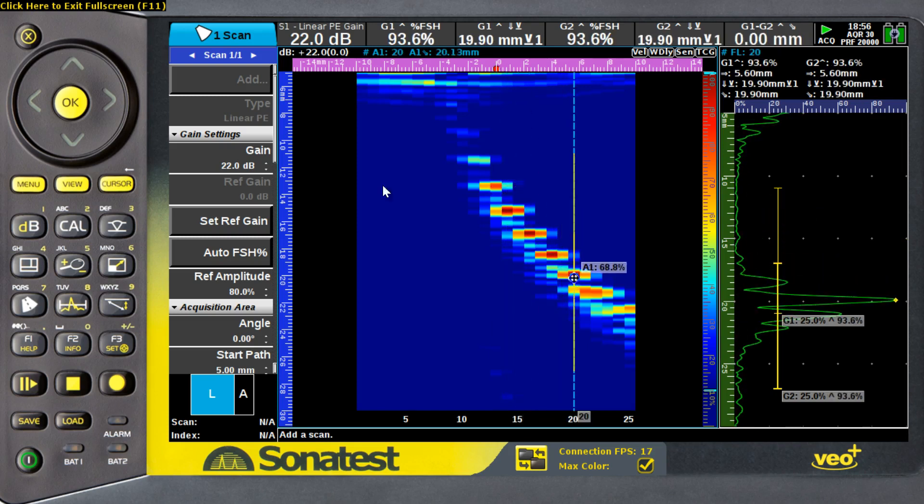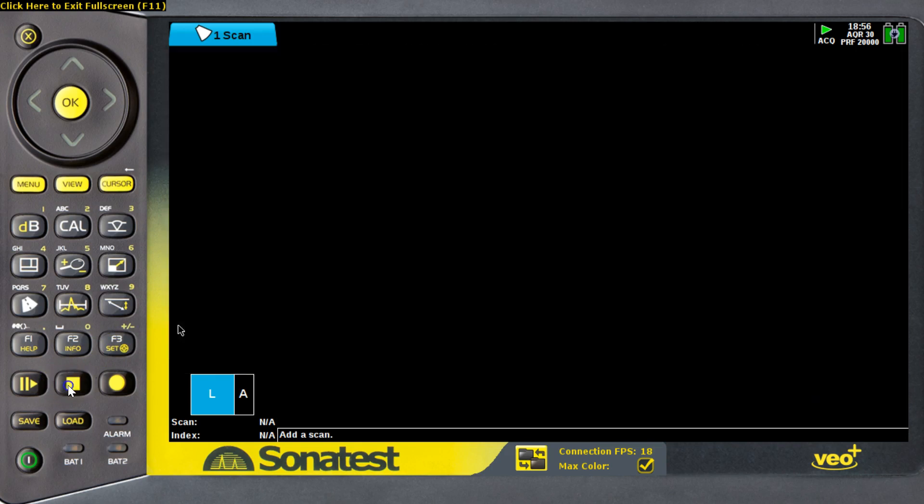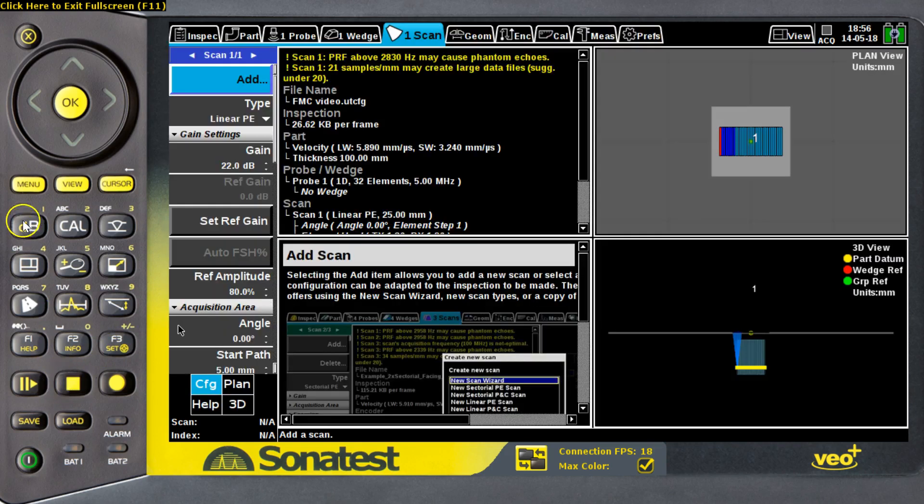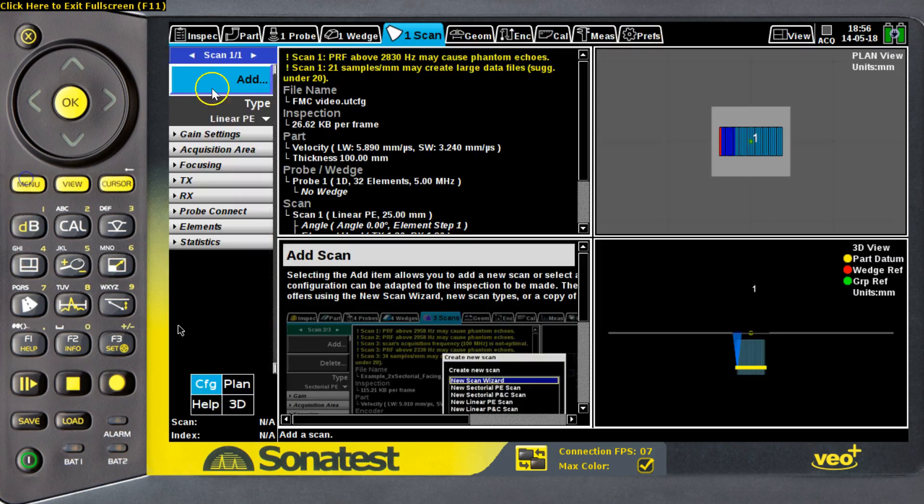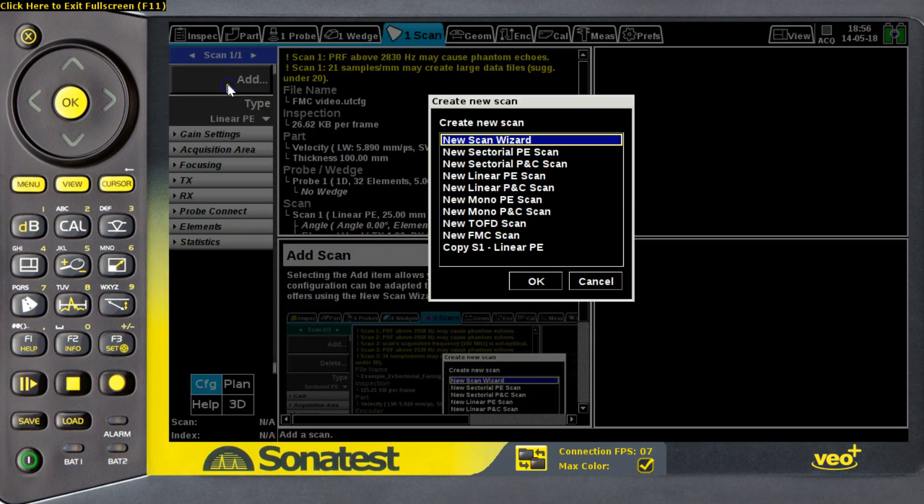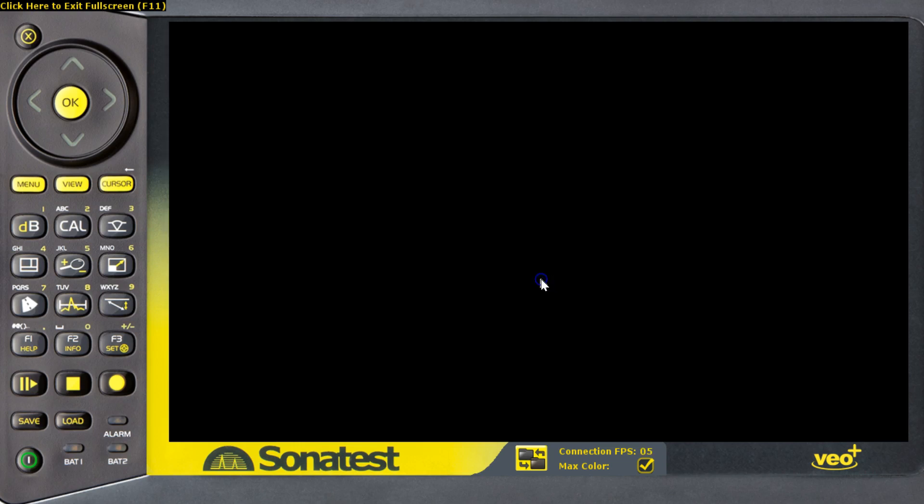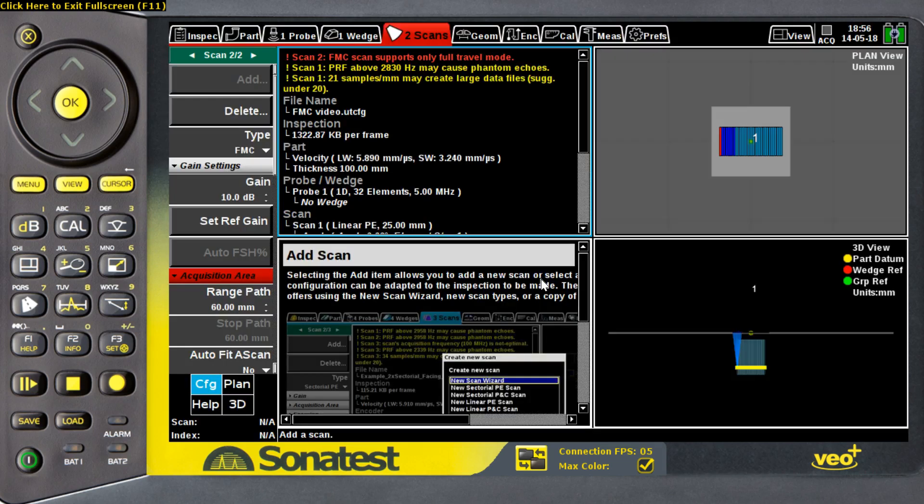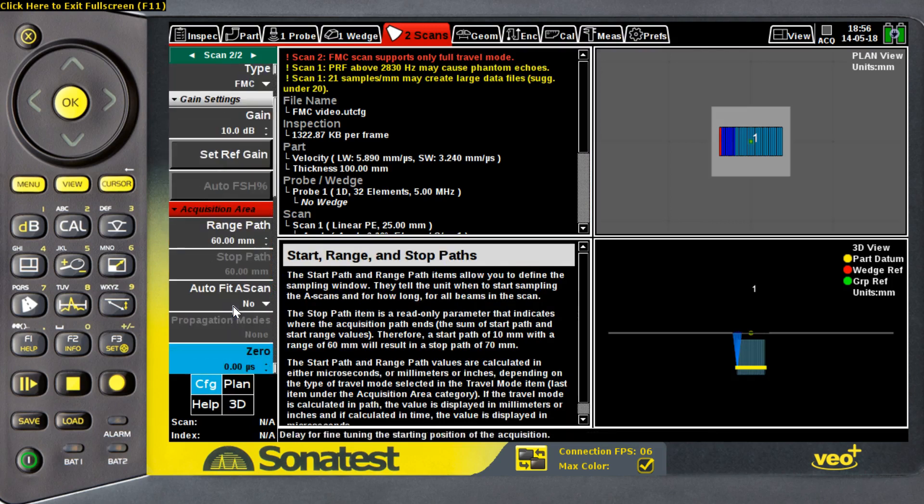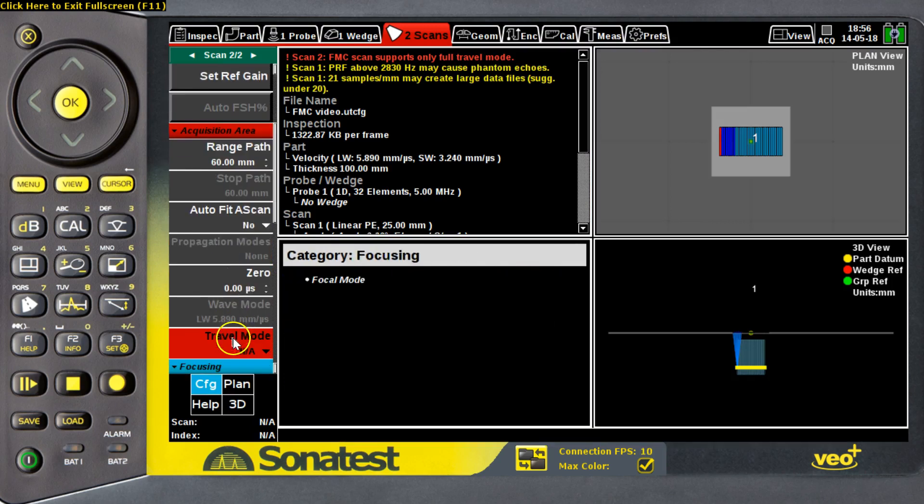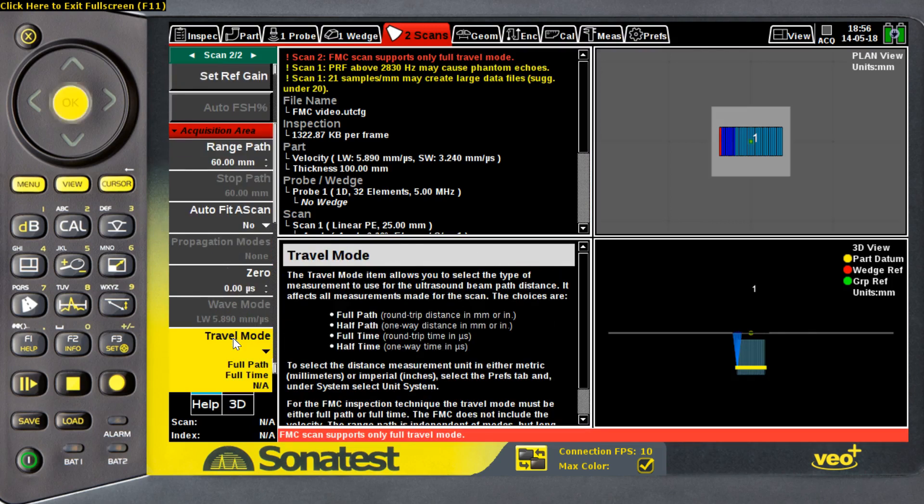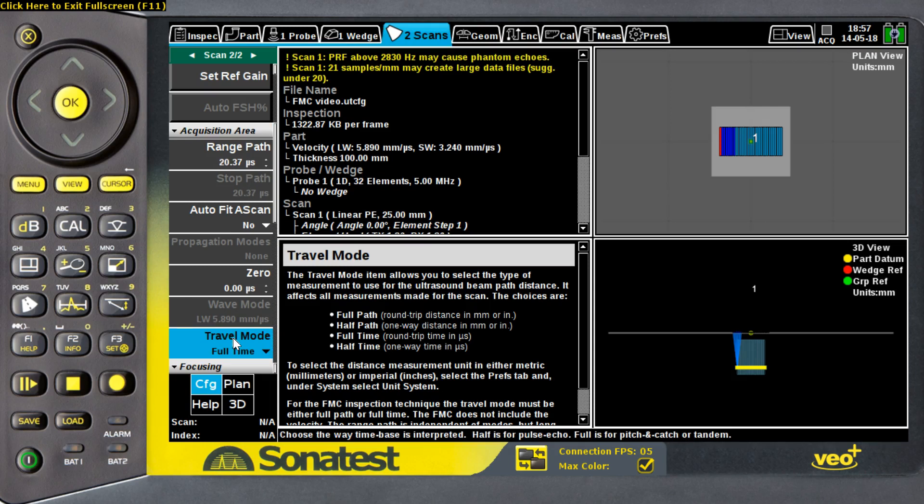Now, because my instrument has the FMC-TFM software option on it, I'm able to create a new FMC scan on my instrument. Creating a new FMC scan will give me the ability to record all the possible acoustic information under the Phased Array probe.